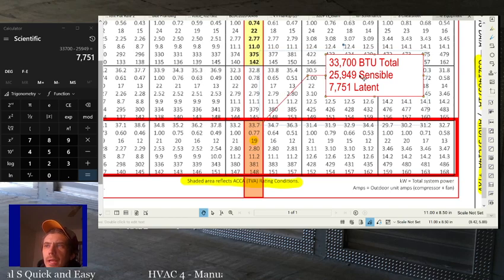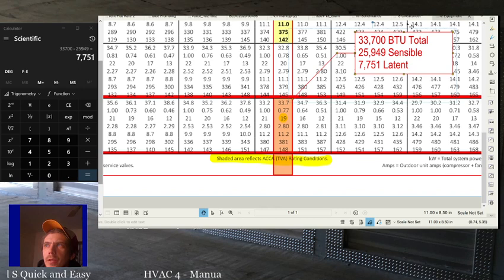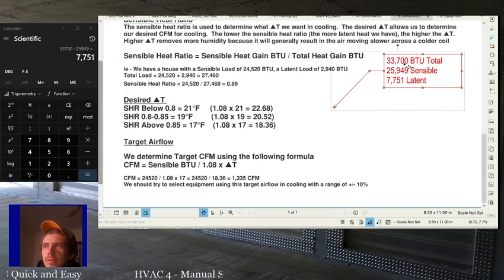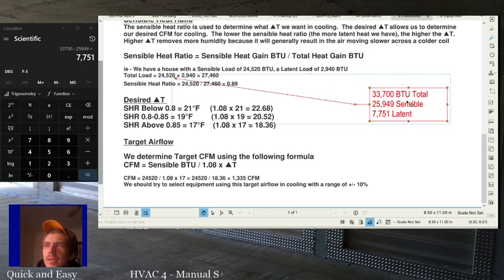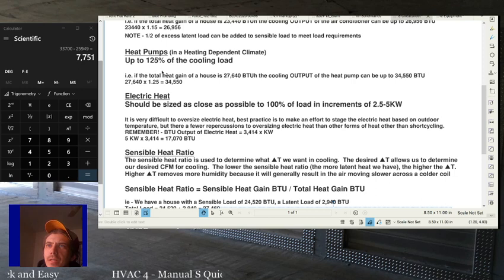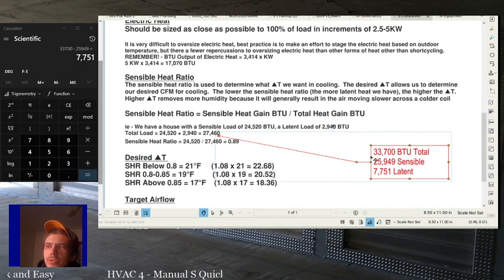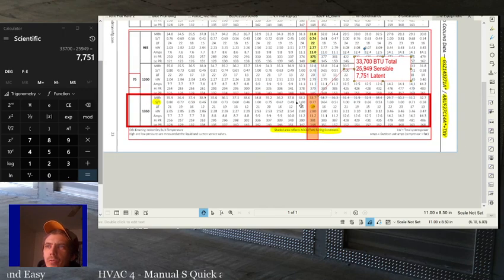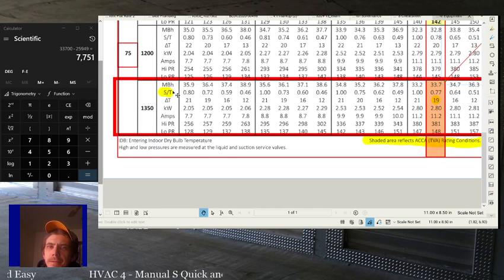All right, so now that we have these numbers at this airflow, we can compare them to the equipment we had, right? So let's just move this over onto our cheat sheet real quick. And we can see that the 25,949 is higher than our 24,520. The 7,751 is higher than the 2,940. The 33,700 is within 125% of our total. So this equipment right here would work at these numbers. All of this would work out. We can put this equipment in, set it at about 1300 CFM, and it'll work. And we'll design our duct then at 1300 CFM. And that's everything going through manual S.